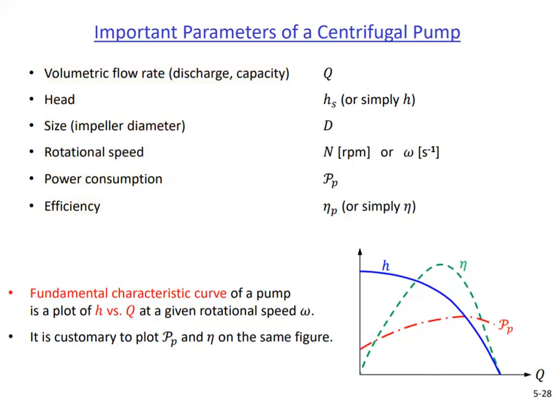H-Q curve of a pump at a certain rotational speed is known as its fundamental characteristic curve. It is the blue curve shown here. It is also possible to show the efficiency and the pump power curves on the same plot. Typical variations with flow rate are as shown here. Actual curves are different for each pump and depend on how the pump is designed.